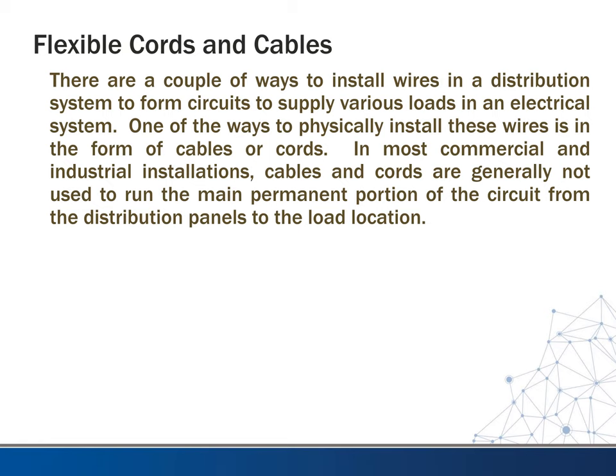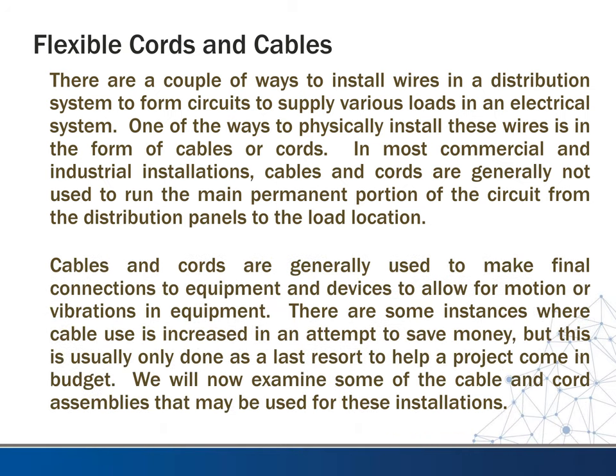There are a couple of ways to install wires in a distribution system to form circuits and supply various loads. One way is in the form of cables or cords. In most commercial and industrial installations, cables and cords are generally not used to run the main permanent portion of the circuit from the distribution panel to the load location. They are generally used to make final connections to equipment and devices to allow for motion or vibration. There are some instances where cable use is increased to save money, but this is usually only done as a last resort to help a project come in budget.